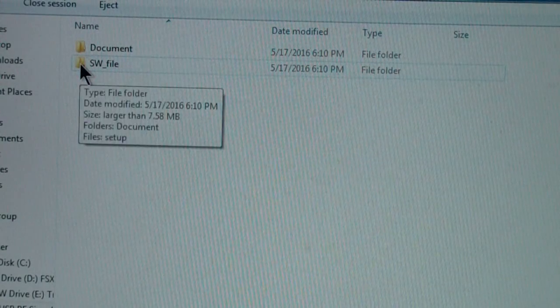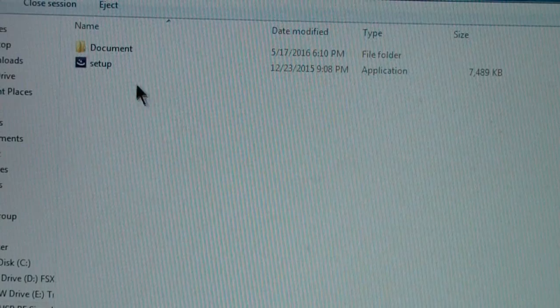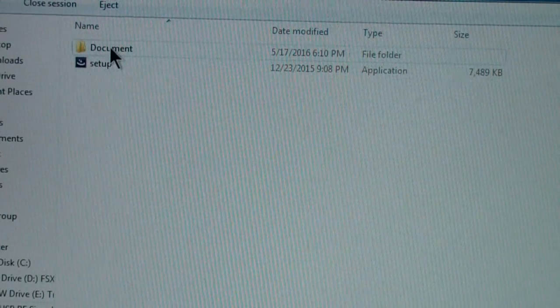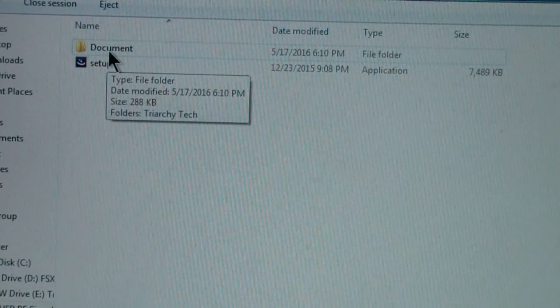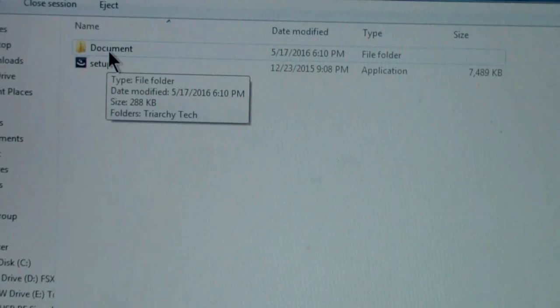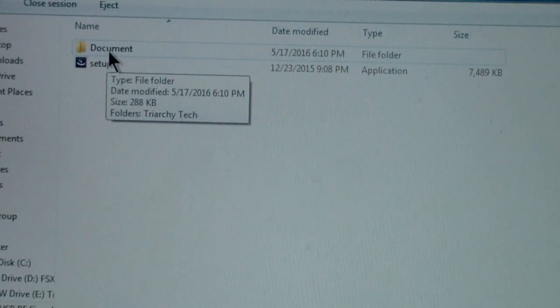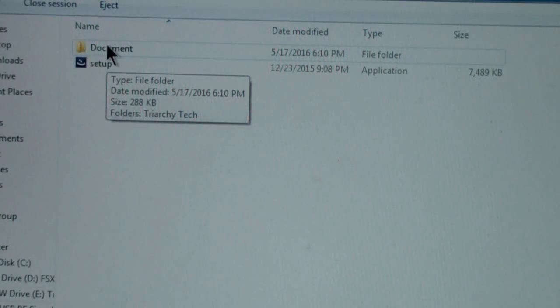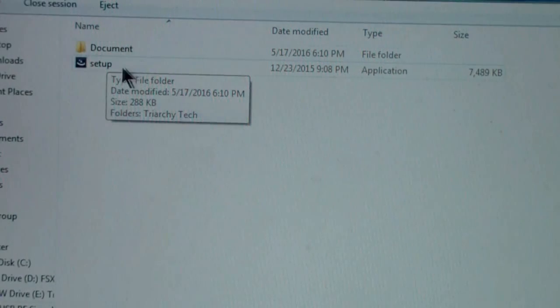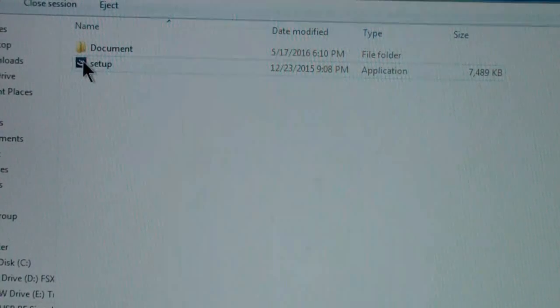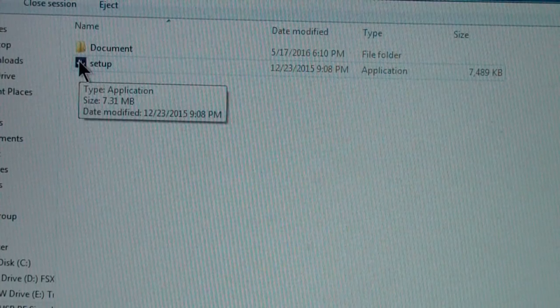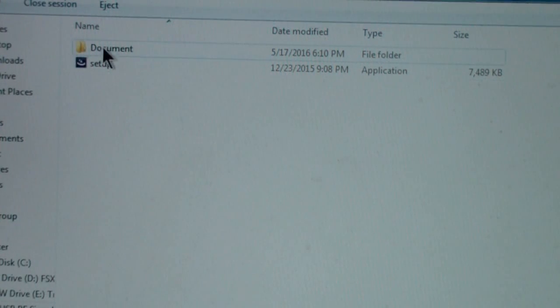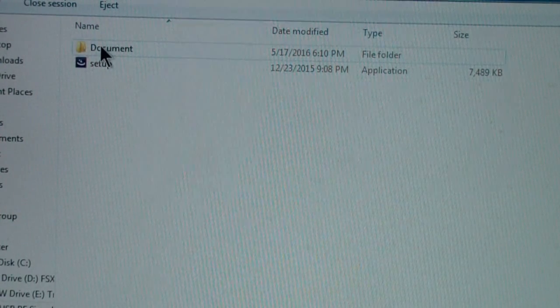Open this up, and you'll see there is a document directory and an SW for software file. Click on SW file and open that, and you'll see setup and the document file. Now, the files for calibrating the unit are in the document file. The important thing is that whatever the file you put this program in, that the setup program and that document file will be in the same directory.